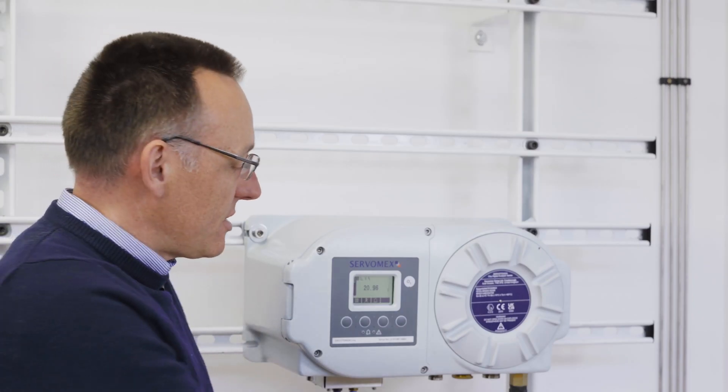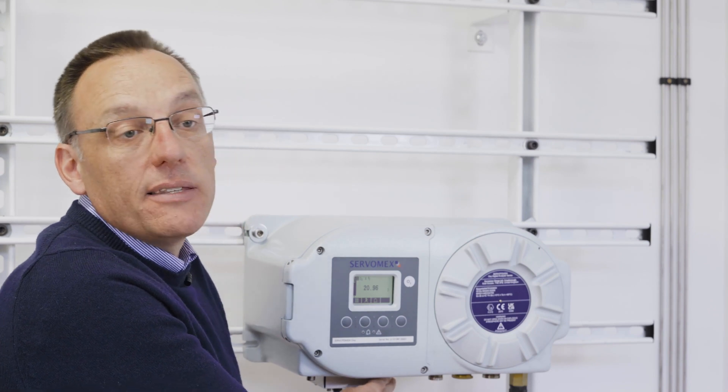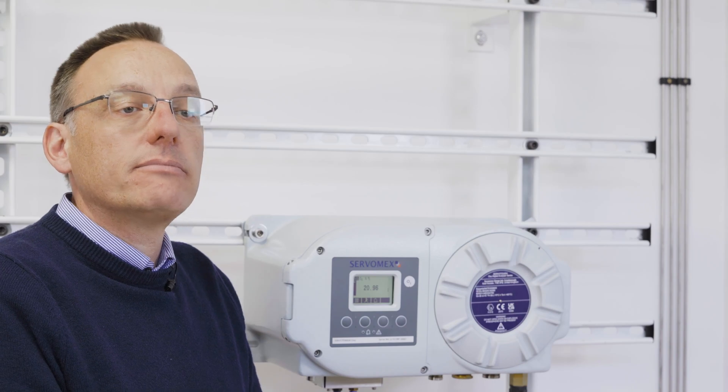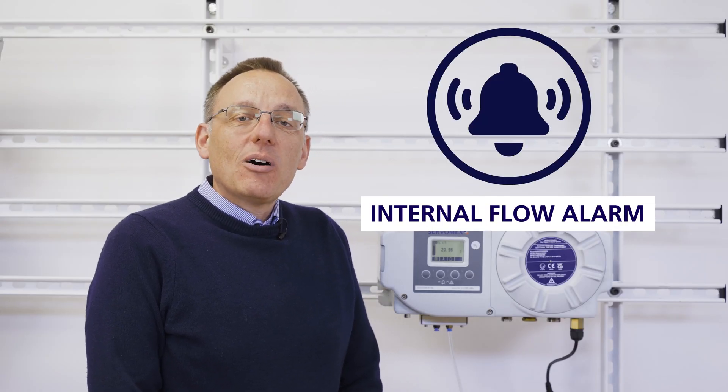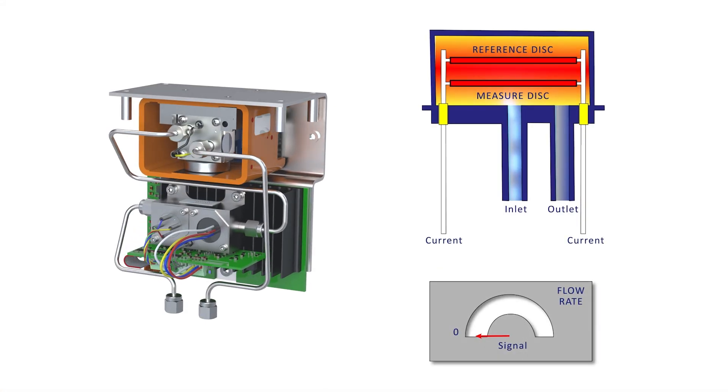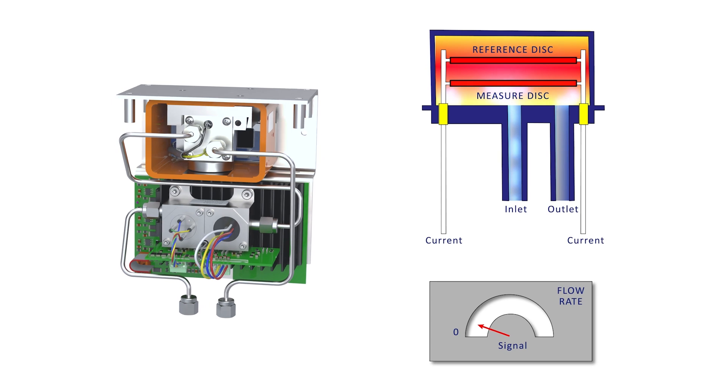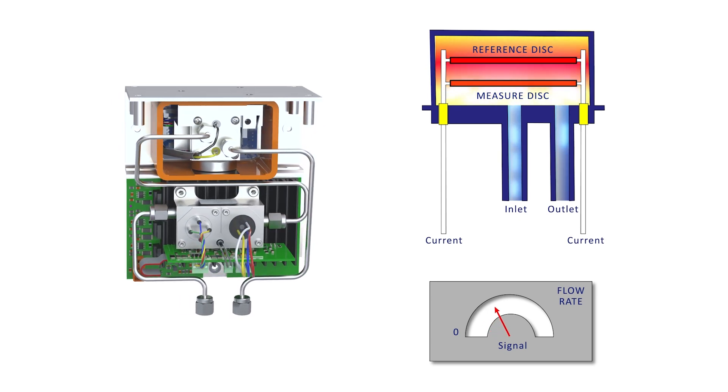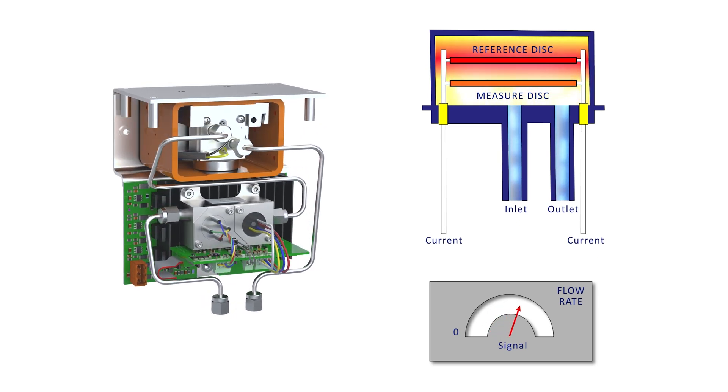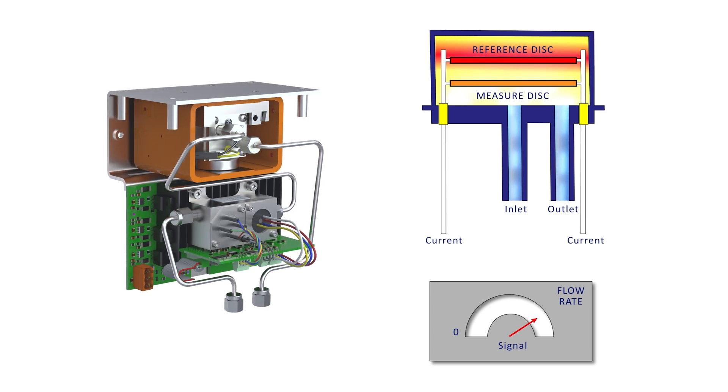Sample flow rate options to the sample gas inlet port are either 200 or 1000 millilitres per minute. There's also the option for an internal sample flow alarm within this compartment. The flow alarm uses a post-measurement Servomex flow cube sensor to validate that the sample has flowed through the paramagnetic sensor itself.